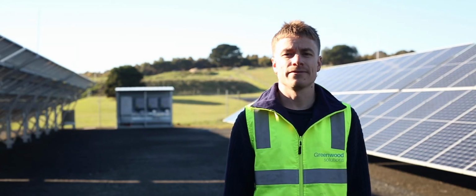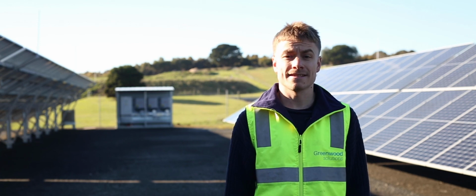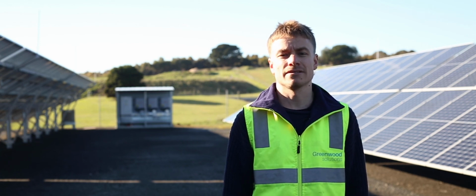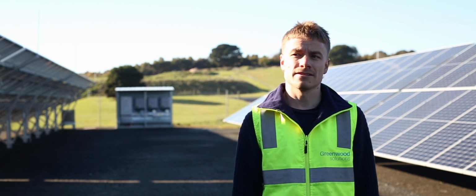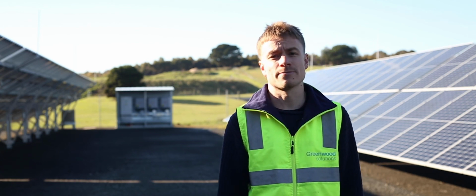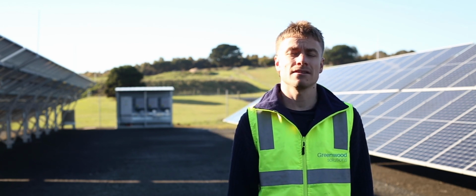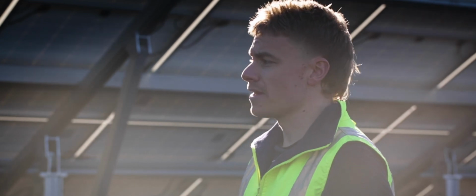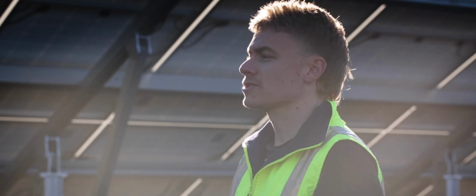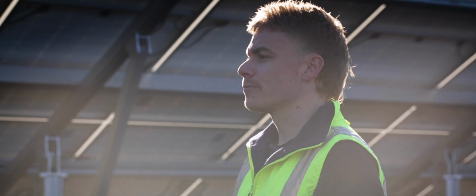Part of the specification for this project was to meet AS 1768's lightning protection level 2. Part of that is installing surge protection devices both on the DC and the AC side. There's also down conductors around the array which join to underground earth electrodes, which all make up a part of the lightning protection system.